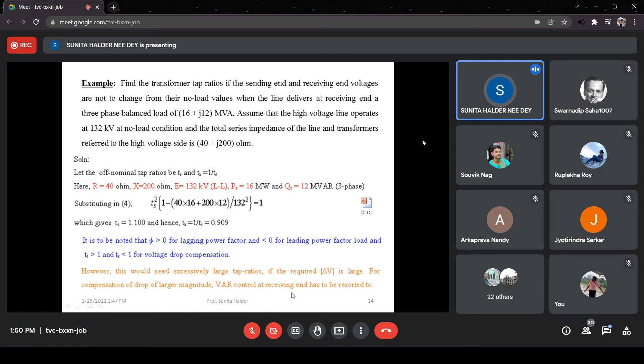So the voltage is 132 kV. Only by changing the tap ratios, we are maintaining the same voltage drop, right? Otherwise we have to change the 132 kV to some higher value. Sometimes very large tap ratios may be needed for a higher voltage drop, but it may not be possible. In that case we may need some other voltage drop compensation means also.